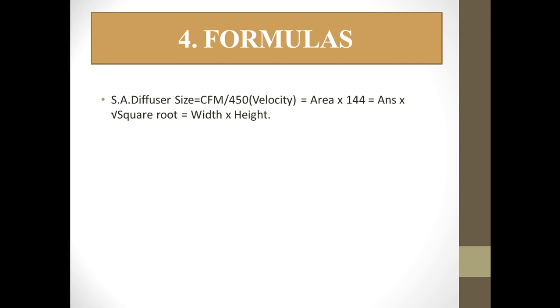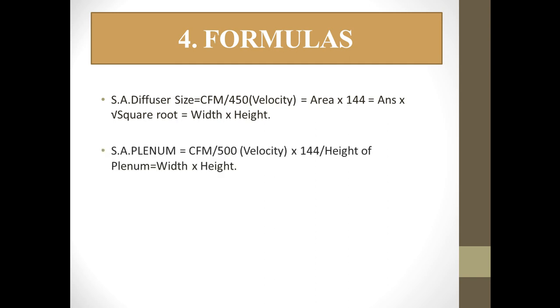To calculate the supply air diffuser size: Supply Diffuser Size = CFM / 450, where 450 is the standard velocity. Calculate the area, multiply by 144, then take the square root of the result to get the dimension. For a supply diffuser, both sides have the same width, so taking the square root gives you the width × height directly.